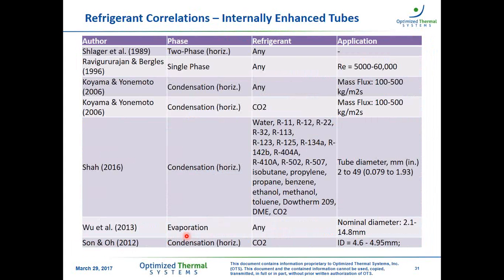Refrigerant correlations. As I said before, small flow channels have been around for quite some time for microchannel heat exchangers. There have been several correlations developed for it. More recently, we've seen some new developments for internally enhanced tubes with small diameter tubes, as indicated here in the table. And basically, with both sets of correlations, that gives us enough tools to create and optimize novel heat exchangers.